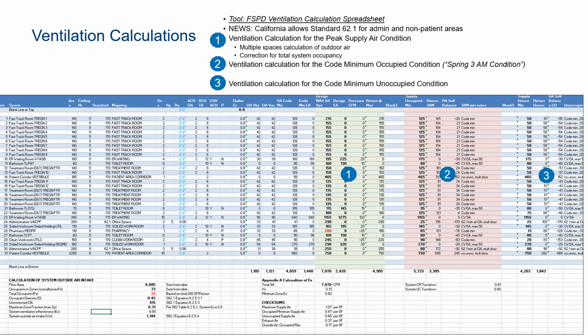And I call this the spring 3 a.m. condition. So you basically assume that it's 3 o'clock in the morning and the temperature outside equals 72 degrees, exactly the temperature inside. So there's no external cooling load, there's no external heating load. Occupancy is at a bare bones minimum because it's 3 in the morning, so you're probably 500 square foot per person or less. And you basically need to identify the minimum CFM and at the same time identify the supply air temperature that you're going to be able to set back to.